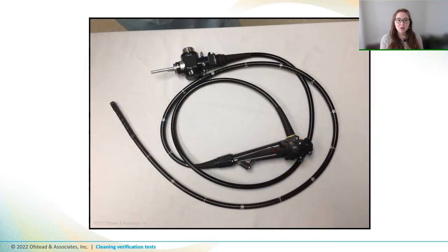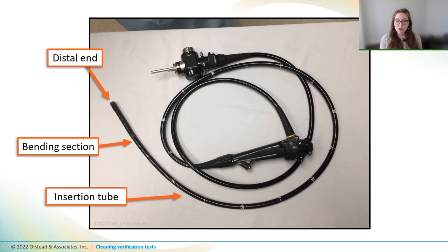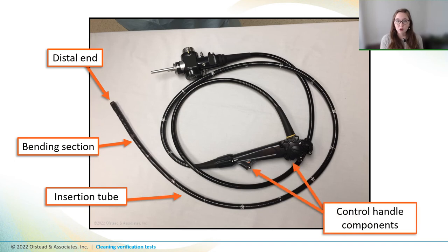And now, although the new standards say we have to do tests to make sure that that instrument channel is clean, we also think it's important to make sure that the outside of the scopes are clean too. In our research studies, we've conducted tests to detect soil on distal ends, bending sections and insertion tubes, as well as control handle components like the ports, valve housings, and the control handle itself.